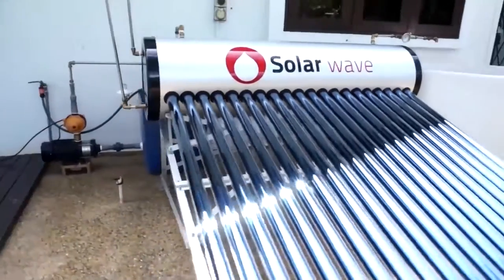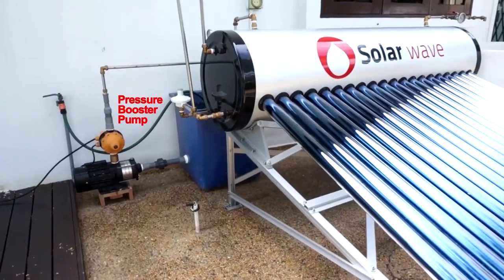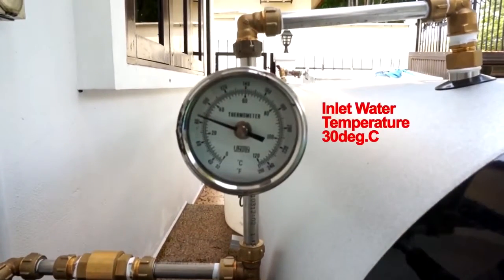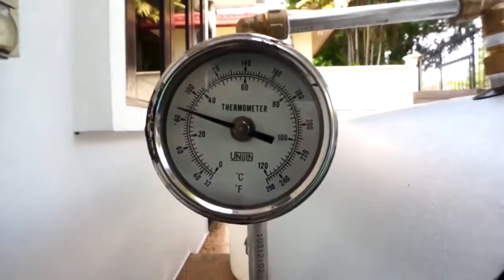This is the setup of our live demonstration unit. A high-pressure booster pump feeds cold water into the system. We'll then monitor the temperature of cold water feeding in, the hot water that comes out the other side, and the volume of hot water produced.